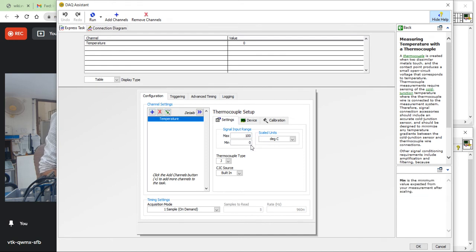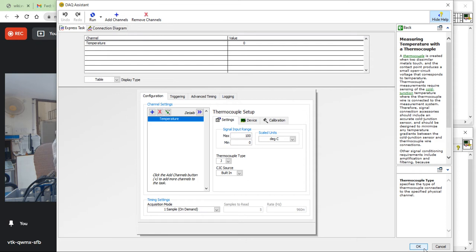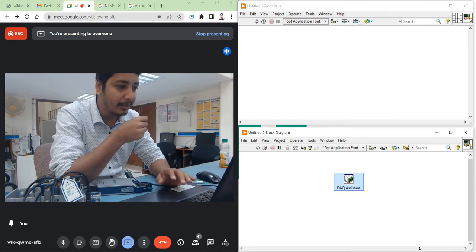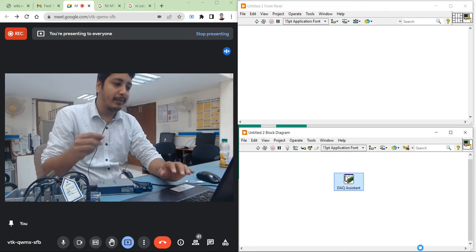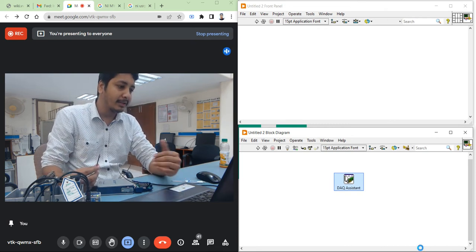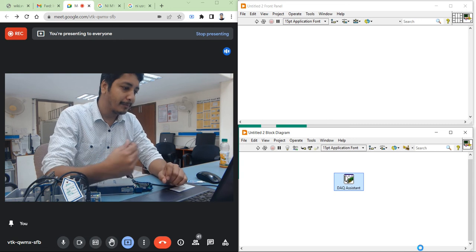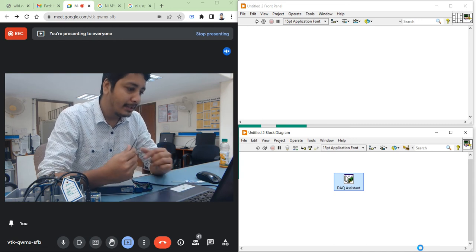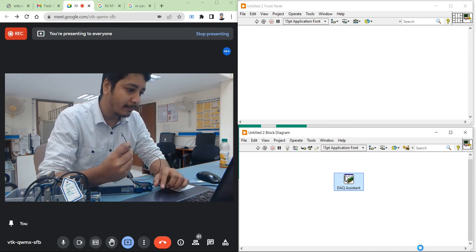In the express task, the measurement type is temperature. The maximum is 100 degrees centigrade, minimum is 0. The thermocouple type is J-type. The acquisition mode is single sample on demand, meaning whenever the user presses the Run button, the system will give the output. So it is one sensor, one sample of data.